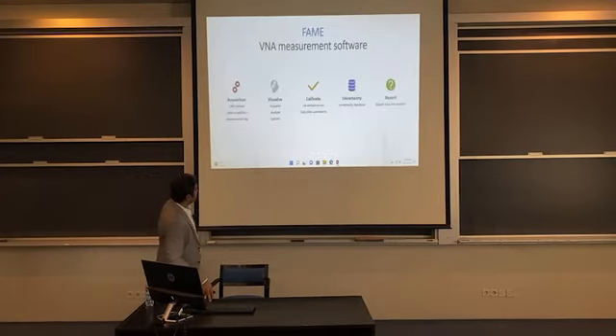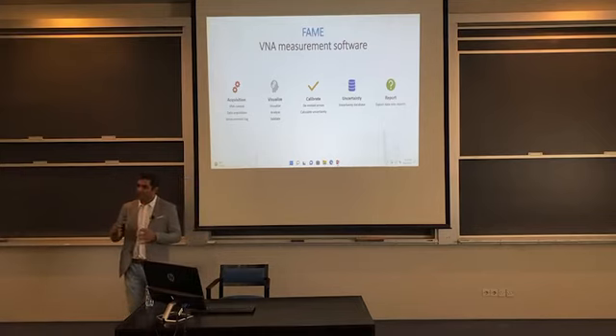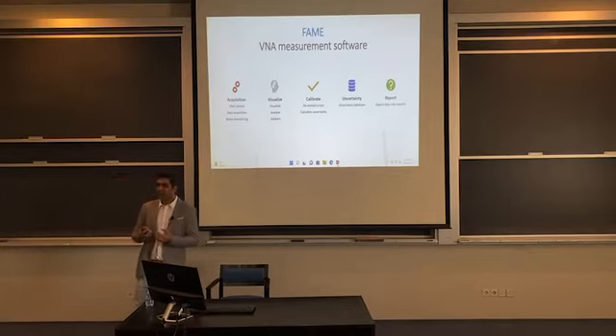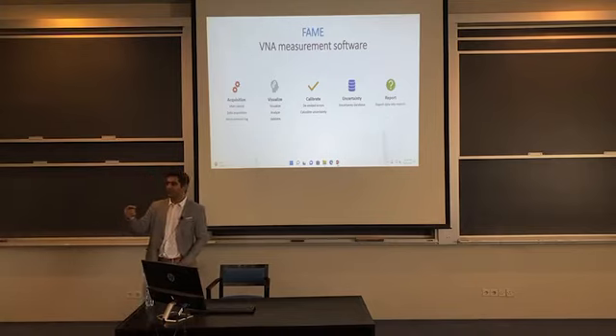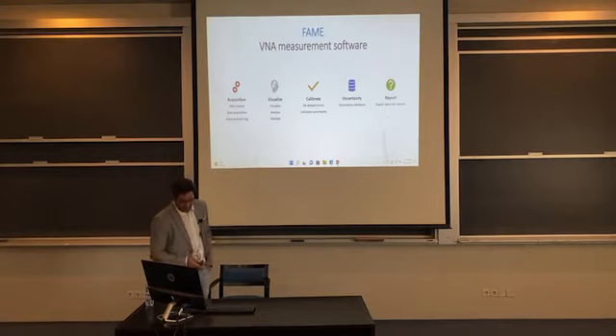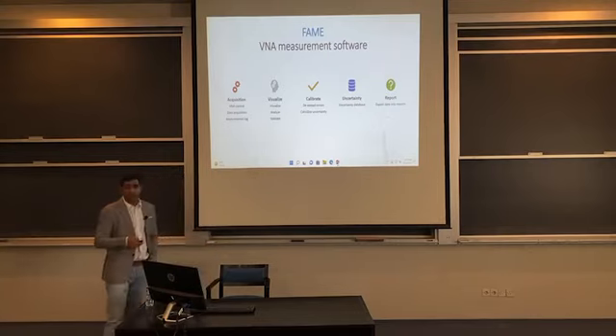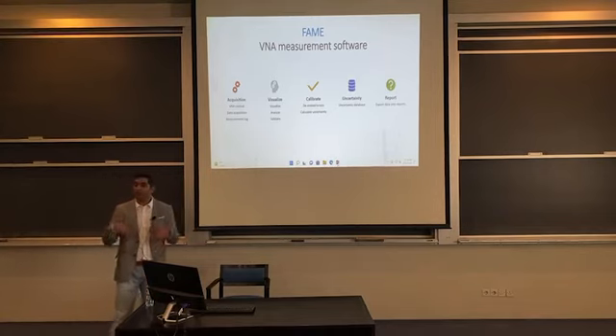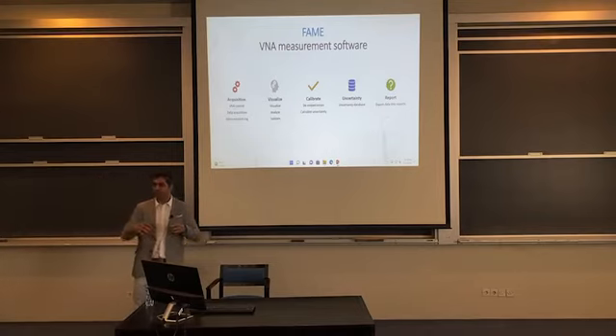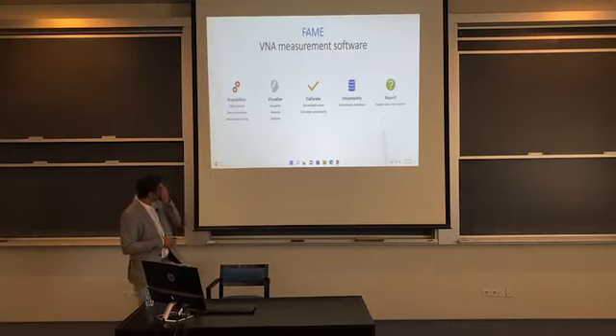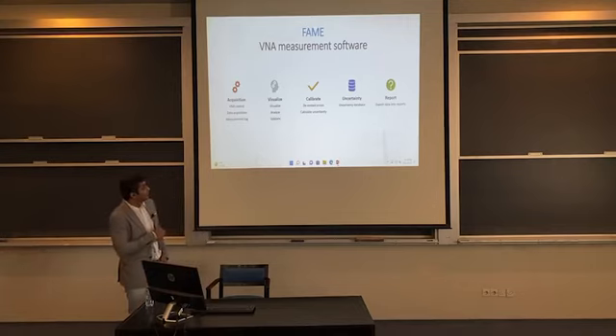Now, I've been talking about connectorized and on-wafer measurement, collecting all of these uncertainty estimates of each and every element involved in this measurement setup, but how to propagate these errors and compute an accuracy of a device under test. So one parameter with one accuracy uncertainty estimation on top. And for that, we basically designed our own measurement software, which is able to acquire the data from the instrument itself. So we collect the data, we don't use the firmware on the instruments, which is provided. We do all the processing on the computers ourselves. And we have a software which is basically responsible for data acquisition. Then we have a module which basically calibrates this data, so de-embeds the error and calculates uncertainty.